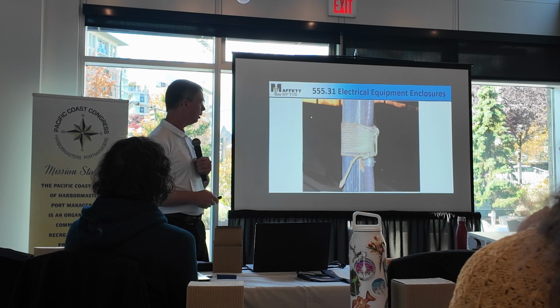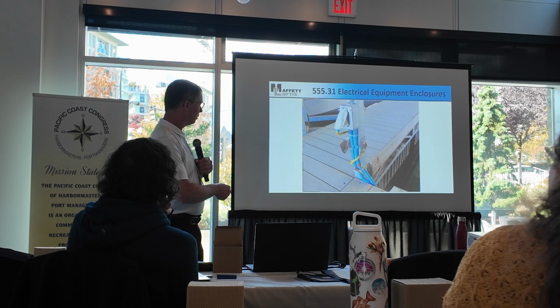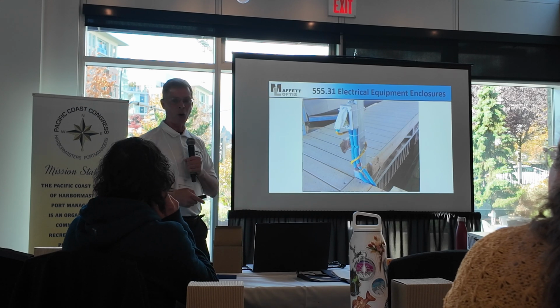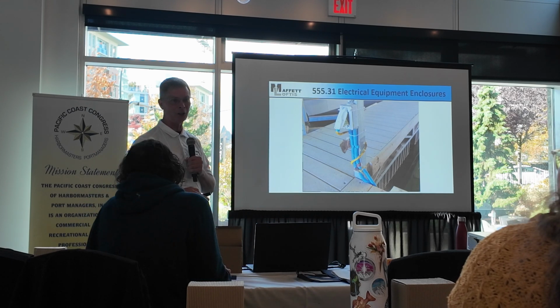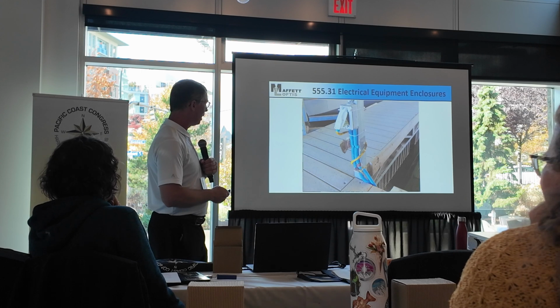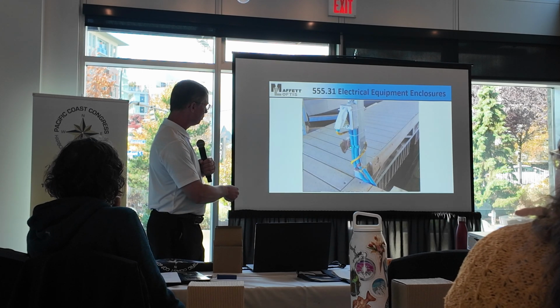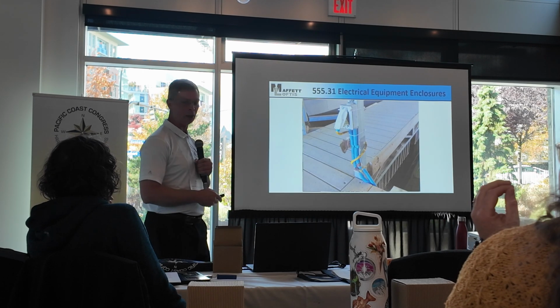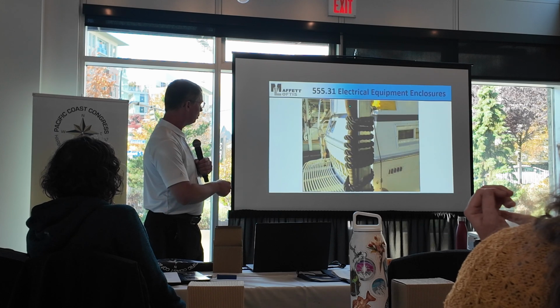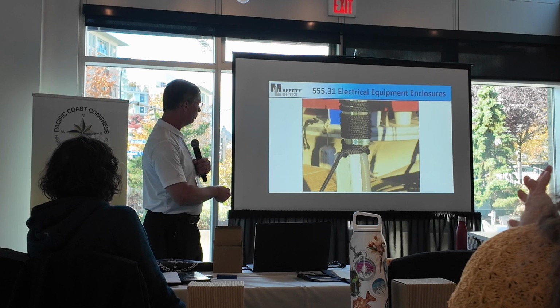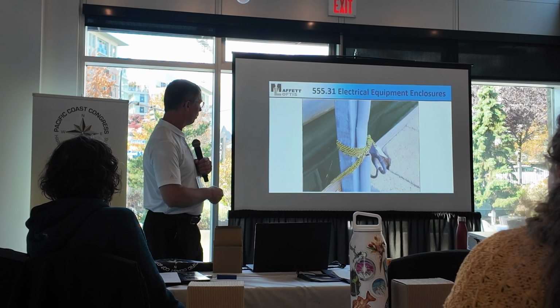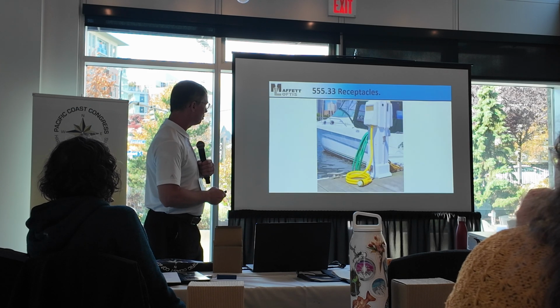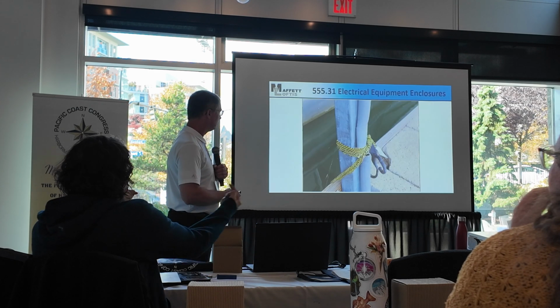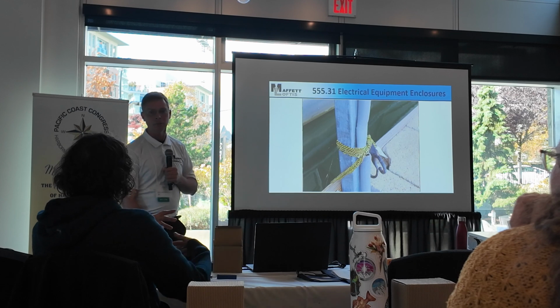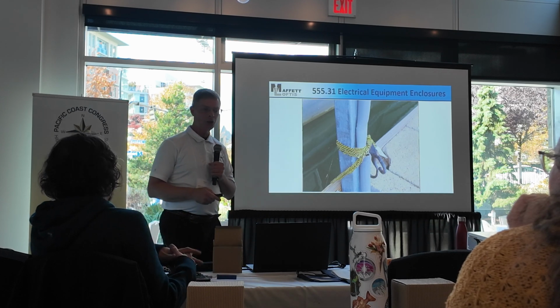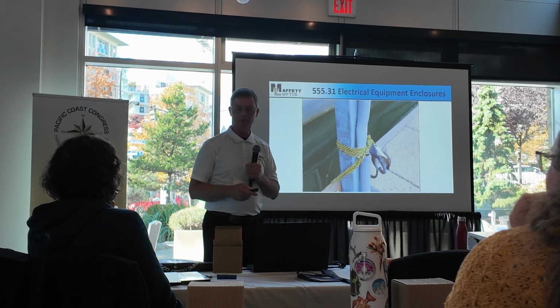Absolutely it is. And the Smurf tube is not code compliant, but people wired them that way back in the day in marinas, and they get damaged. But you can see where the worn cable was. Look, they smashed it like crazy. What about this one? Or that one? Nice. Or that one? And it's everywhere. I saw one that had the electrical cord actually wrapped around that. Would that cause anything further? Generally not. No, generally not.